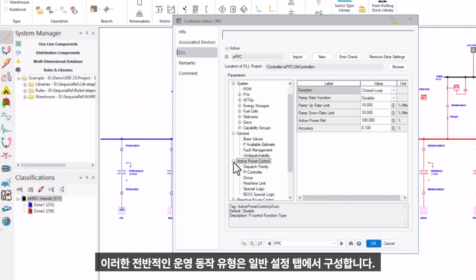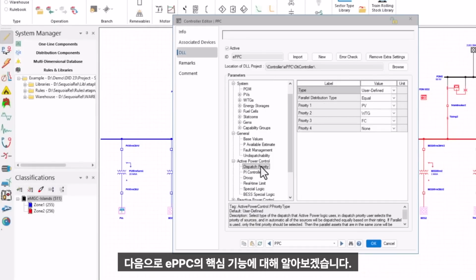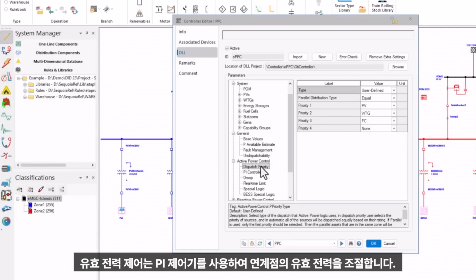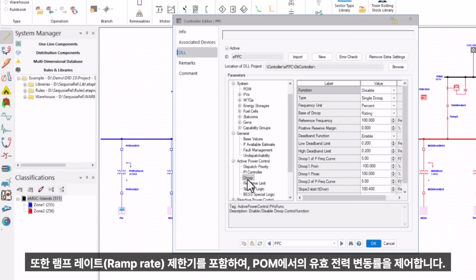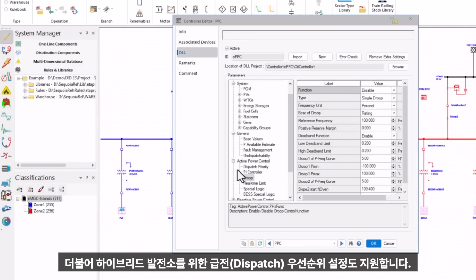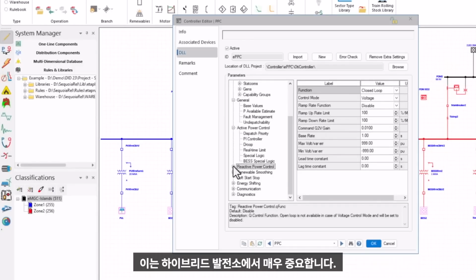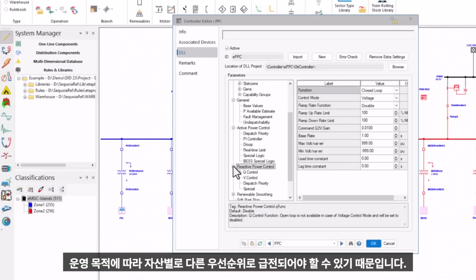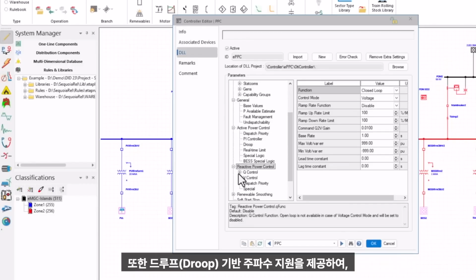Next, let's talk about core functionalities of ePPC. The first one is active power control. Active power control uses a PI controller to regulate active power at the point of interconnection. It also includes a ramp rate limiter to control the rate of active power change at the POM. In addition, it supports dispatch priority settings for hybrid plants. This is especially important in hybrid plants where different assets may need to be dispatched with different priorities depending on the operation objective. It can also provide droop-based frequency support, adjusting output power in response to grid frequency fluctuations.